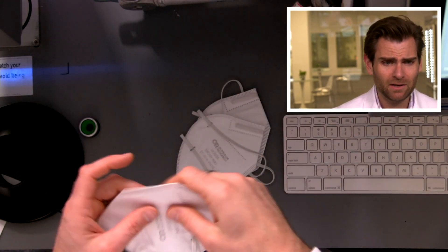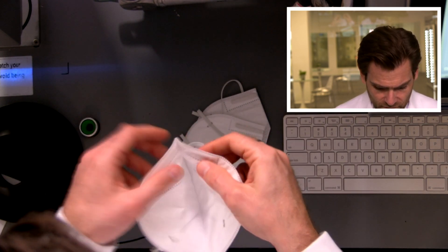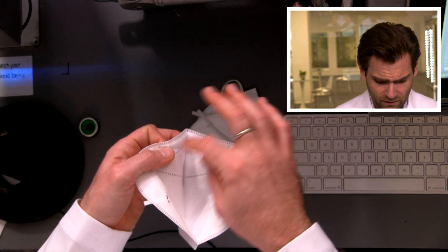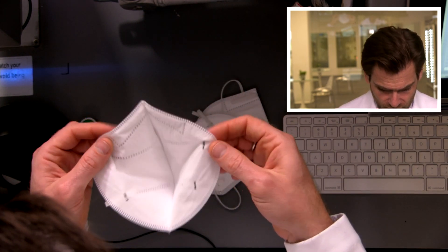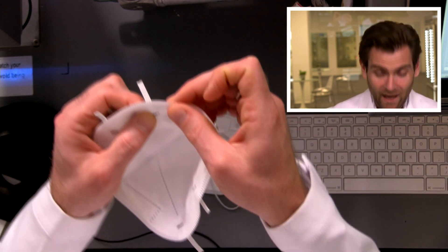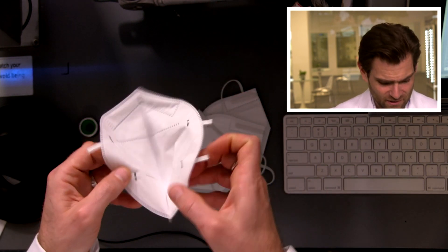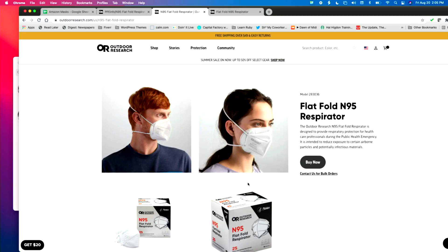They say it's made in the United States. I don't know much about this company — I thought they were more of a brand. This is a KN95 design. I'm actually pretty surprised that this was able to get NIOSH without a nose foam on it, because typically you need nose foam to get that extra seal. Also, the staples go right through — I can actually see the holes — which means there would be some leakage there. But it's got the TC number, and looking at their website, it does appear they have an N95.